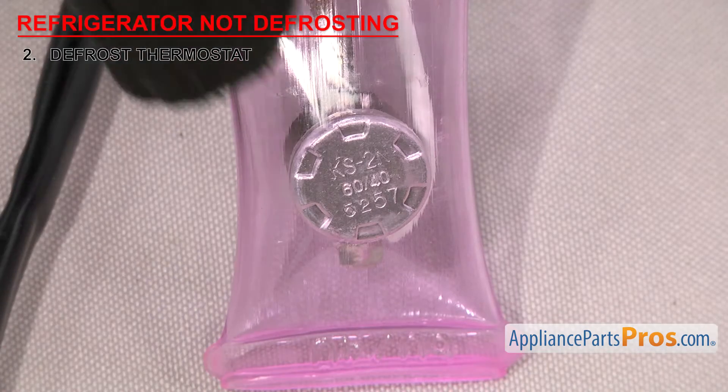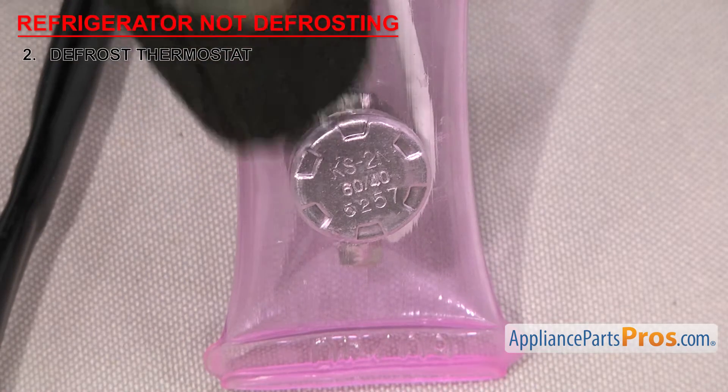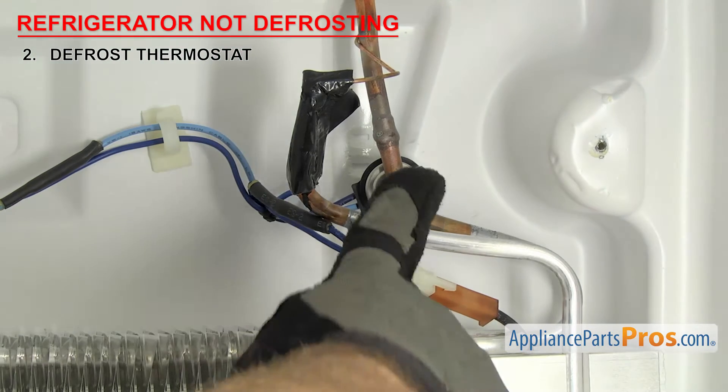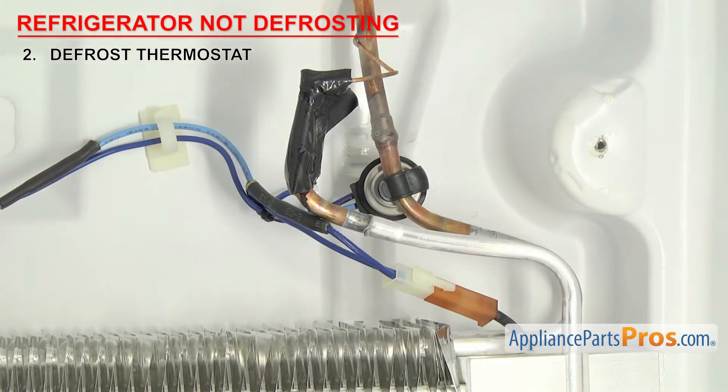This one's rated at 60-40 Celsius. That means it shuts the power off at 60 degrees Celsius and turns the power back on when it cools down to around 40 degrees Celsius. Once the temperature goes below that, the power to the heater is restored. The thermostats are usually mounted behind the back wall of the freezer section on the evaporator.